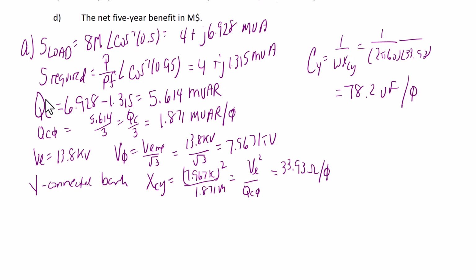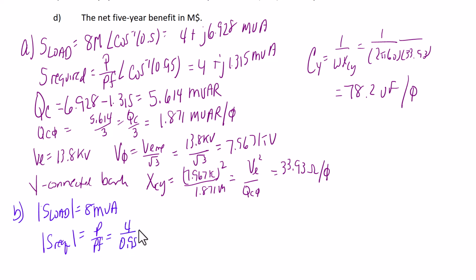So for part B, the annual saving in demand charge, we need to find the apparent power required and the apparent power at the load. The apparent power at the load is 8 MVA, and the apparent power required is P over the power factor, or 4 divided by 0.95, which is 4.211 MVA. So delta S is equal to S_L minus S_R, or 3.79 MVA.